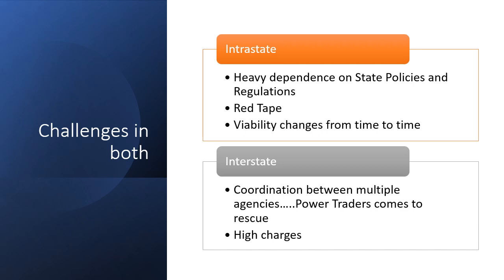With interstate open access, you are more immune to state-level changes because you're connected at a high voltage level and dealing mainly with Power Grid, which is highly digitized. However, if connected at a lower voltage level like 33 kV and procuring through interstate open access, you'd be coordinating with multiple agencies and load dispatch centers. Power traders can help coordinate, but the additional charges mean the landed cost of power at your plant would be very high — and exchange power is often not viable for industries in most Indian states today. The choice of intrastate versus interstate ultimately depends on the industry, and good consultants and power trading companies can help identify the best option.